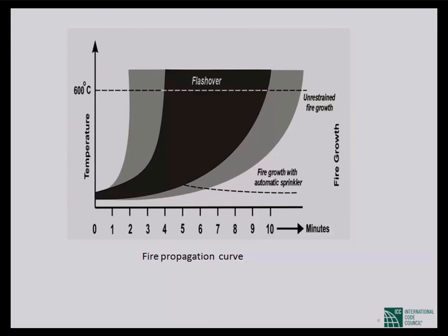So whatever I design or you design, you have to design keeping in mind that the temperature will rise up to that limit and within this time. If you think about life safety issues, whatever you do, you have to do within 10 minutes. If it is beyond 10 minutes, it will be very difficult to save life from that compartment.